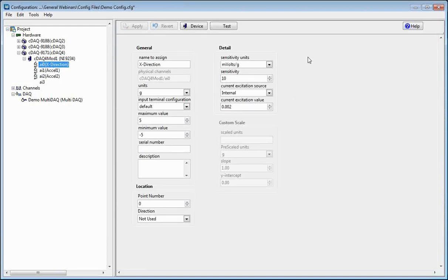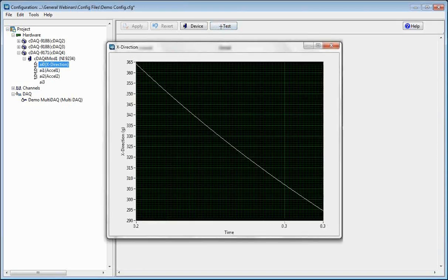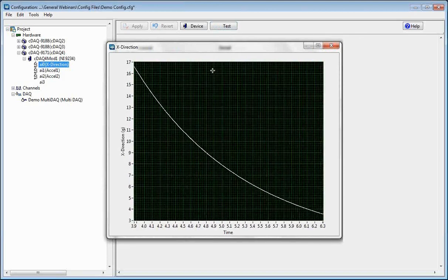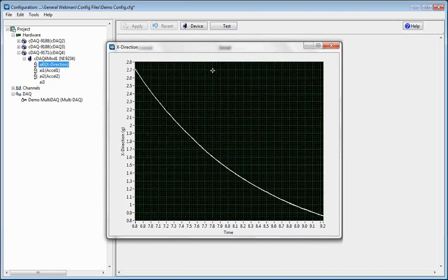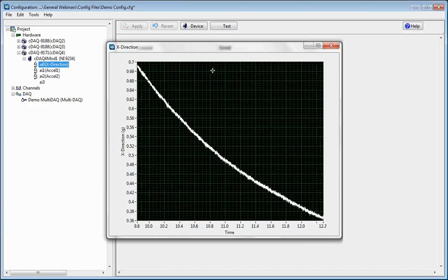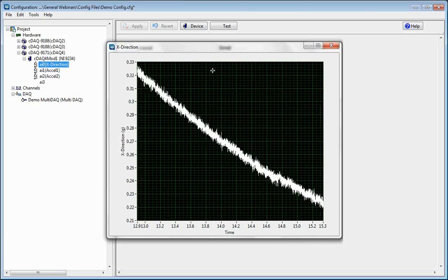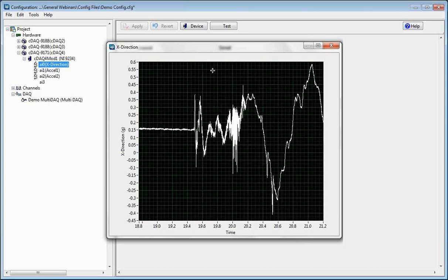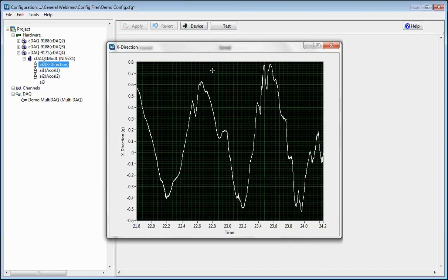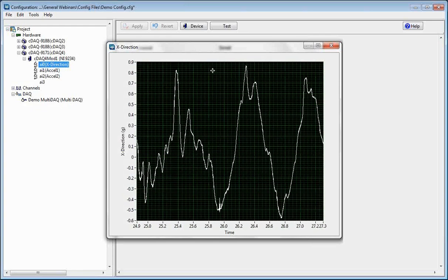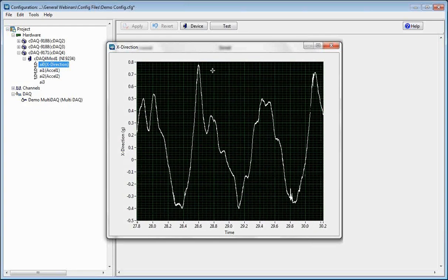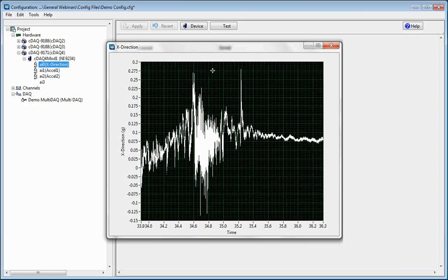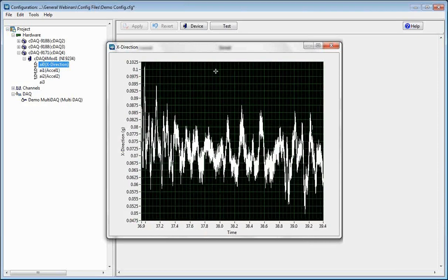The other thing you can do once you have it applied is actually test that channel out. If I just press the Test button right here, it's going to give the accelerometer a moment to charge up and balance out at about zero. If I start moving this up and down, I am indeed showing a change in acceleration with this accelerometer. That's just a quick way to test that the channel is applied correctly and that you are getting the data you're expecting when you perform the test.